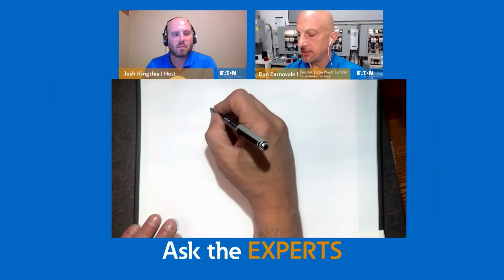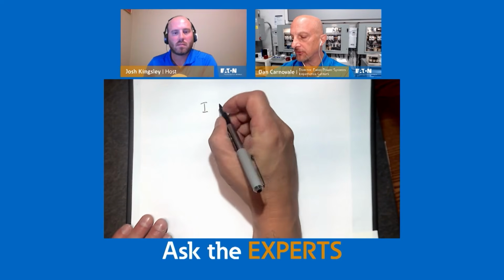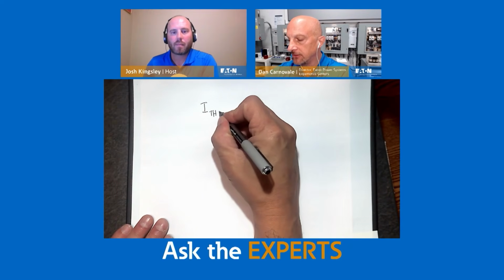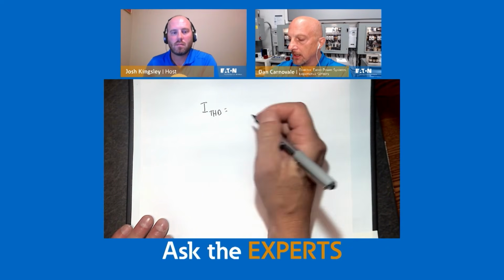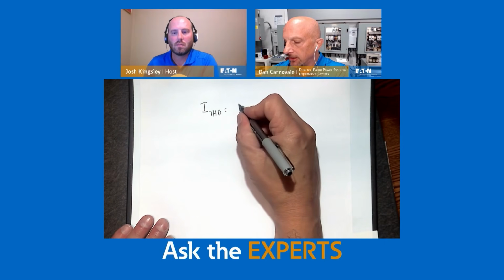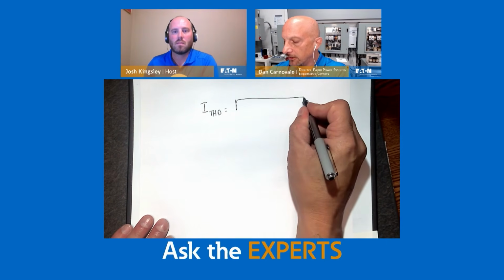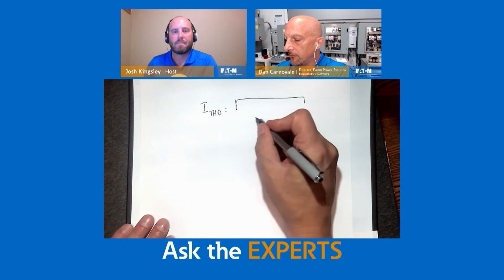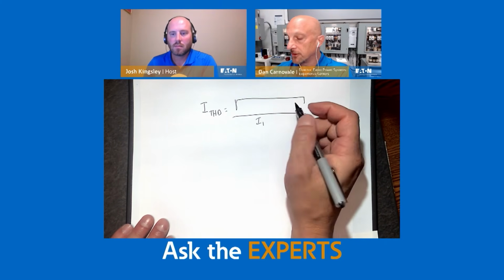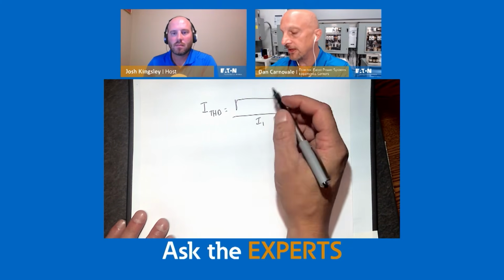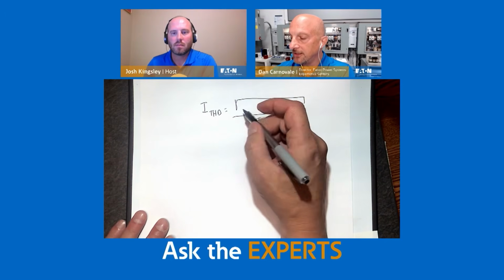Okay. I'll draw this out on a different sheet here. The TDD really gets addressed in the 519 standard. So THD is going to be all of your harmonics squared, divided by the fundamental. And again, you can do this for voltage or current, but in this case, for TDD, we're only talking about current.